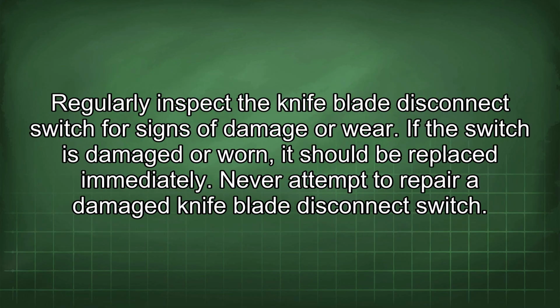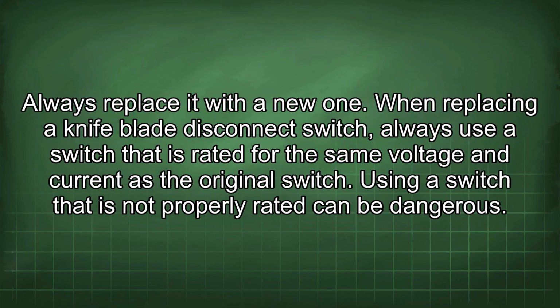Regularly inspect the knife blade disconnect switch for signs of damage or wear. If the switch is damaged or worn, it should be replaced immediately. Never attempt to repair a damaged knife blade disconnect switch. Always replace it with a new one. When replacing a knife blade disconnect switch, always use a switch that is rated for the same voltage and current as the original switch. Using a switch that is not properly rated can be dangerous.